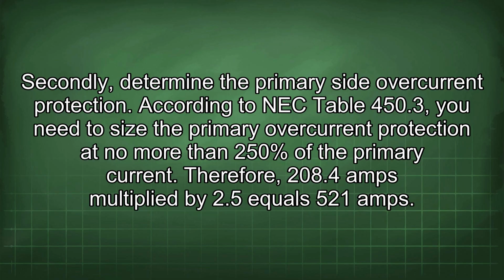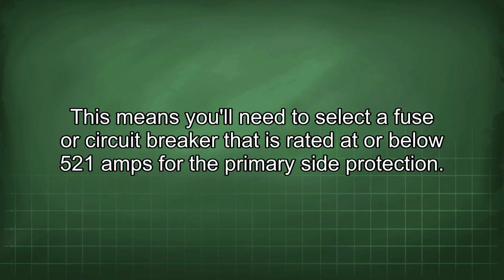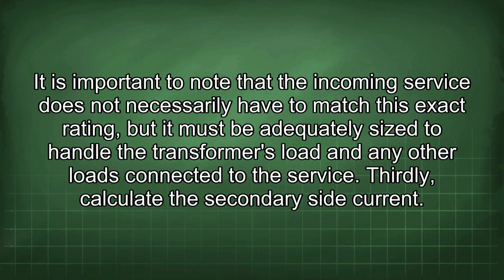Secondly, determine the primary side overcurrent protection. According to NEC Table 450.3, you need to size the primary overcurrent protection at no more than 250% of the primary current. Therefore, 208.4 amps multiplied by 2.5 equals 521 amps. This means you'll need to select a fuse or circuit breaker that is rated at or below 521 amps for the primary side protection.